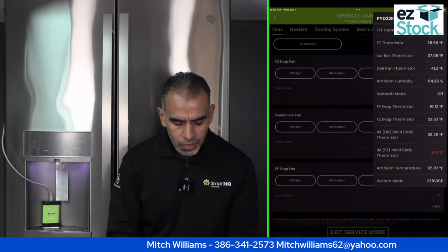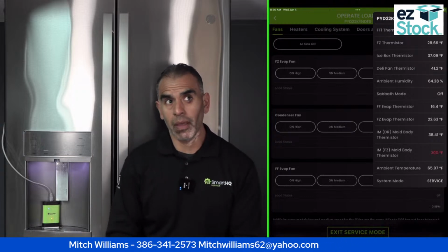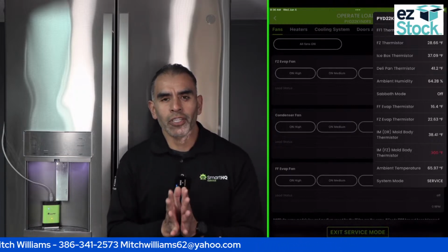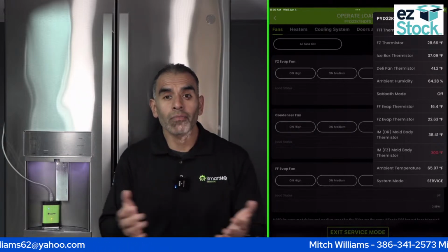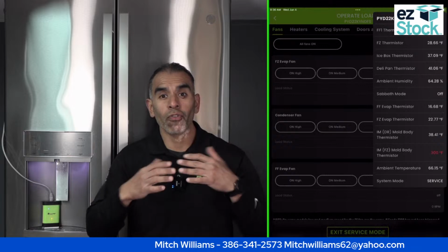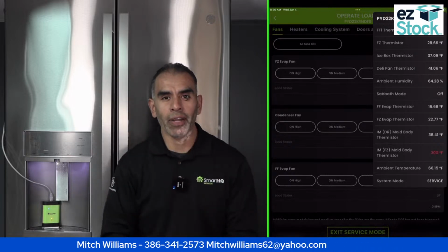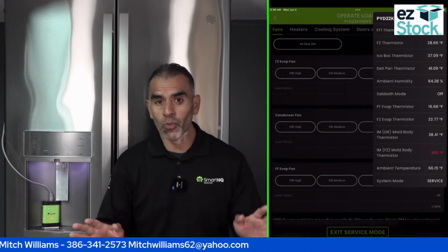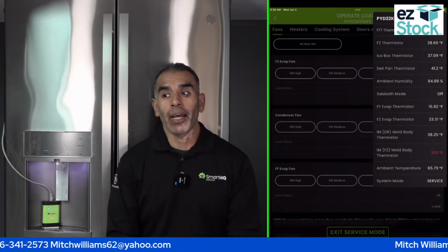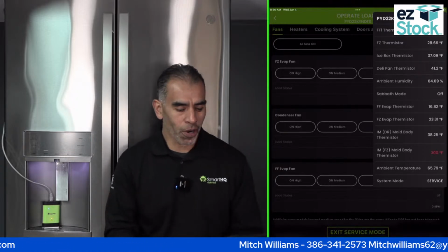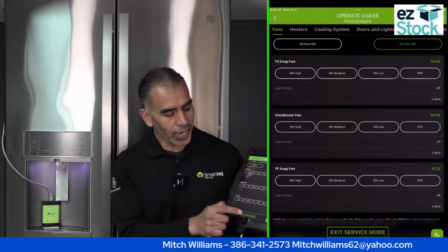A lot of us in the field, myself included, used to check the sealed system by taking the food out of the compartments, pulling the evaporator cover off, and looking for a nice, even frost pattern to verify refrigerant is going to the evaporator coils. That's hands down the best way to verify, but it's also extremely time consuming. So I'm going to show you an alternative way using SmartHQ service. Let's go ahead and exit service mode.